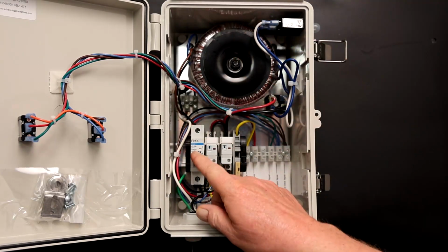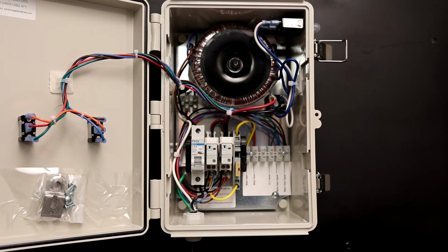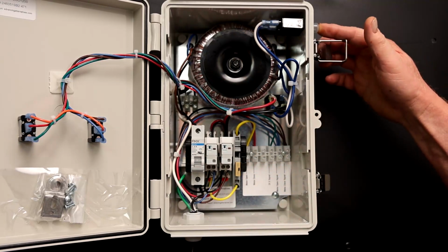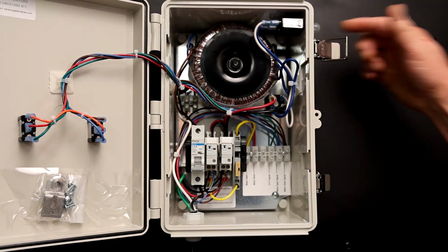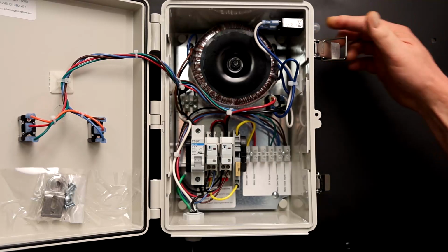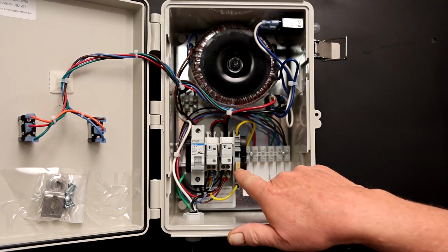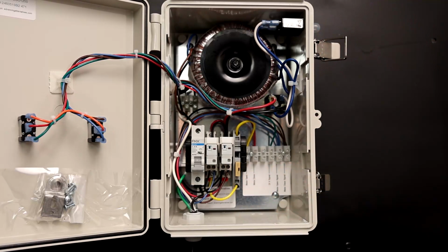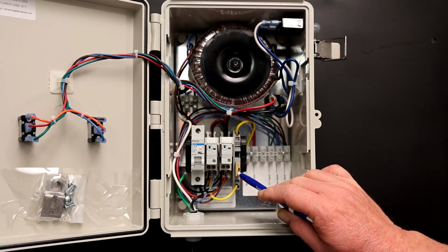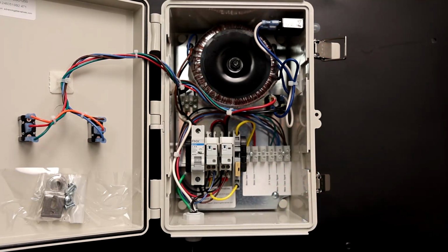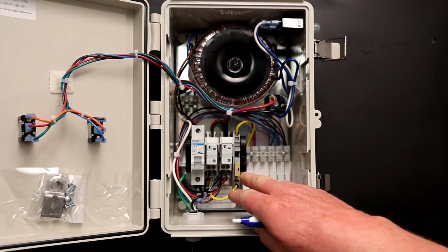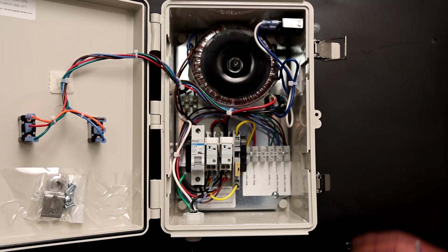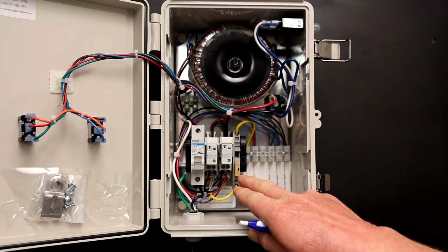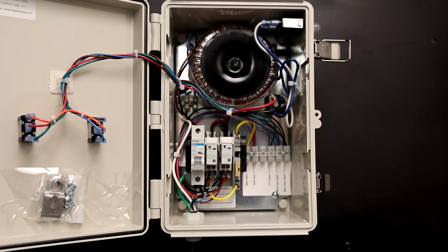The main breaker operates like any other circuit breaker. The secondary breaker will have a button that pops out if it trips. It can be reset by pushing the button, and the same for the motor breaker. The motor breaker varies in value for different motors. For troubleshooting, the first thing to check is the motor breaker. If the motor breaker is good, check the other 2 breakers. Usually the motor breaker will be popped first.